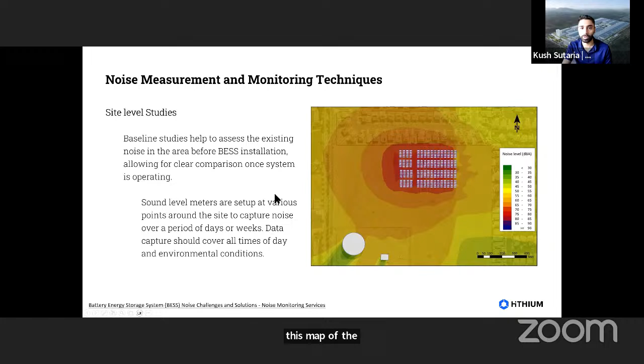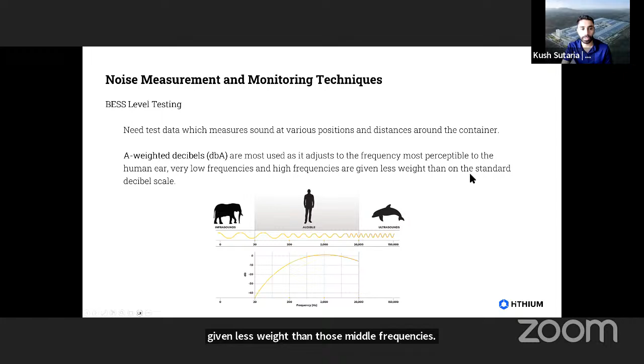When you go to a manufacturer, like Hithium or Wärtsilä, they'll be able to provide you sound data based on testing. It's important to work with the manufacturer, get those data sheets, and make sure you understand them. Generally what's provided is A-weighted decibels, which differ from standard decibel levels in that the human ear is more perceptible to certain frequencies than others. The dBA scale adjusts for that, so very low and very high frequencies, which the human ear isn't as good at picking up, are given less weight than the middle frequencies. That's something to look out for on these data sheets.